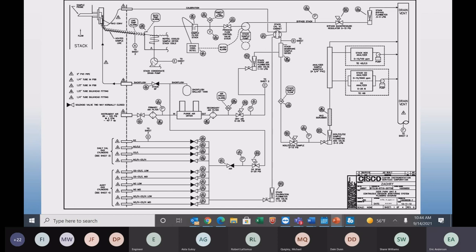But again, here's our drain pump. If that tubing's not changed on an annual basis, you could get a leak right here. They'll suck air up here, and you know, guess what? You'll also get the condensate not draining out, and it's going to go here in the filter and give you a water alarm. Shut the pump off. Hopefully, the pump is plugged into its dedicated circuit. I've seen plenty of times that's not plugged into the dedicated circuit, and you're going to get a water alarm and you're going to pump water into the analyzers.